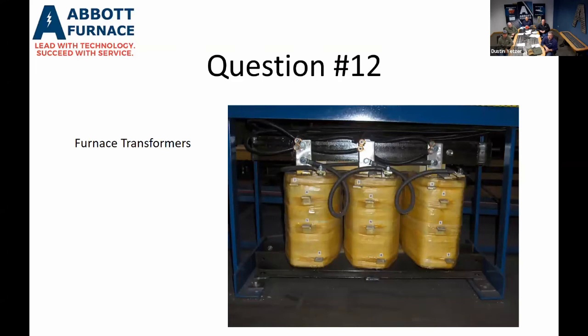You want to look at that zone when it's calling for 100% output and record what the voltage is and the current coming out of the SCR going out to the transformer. You have to determine what size transformer you have in that zone to look at what your max amperage allowed is. Then, as the glow bars wear, the resistance goes up. So if that resistance has increased enough that you're not pulling enough power to heat that zone up, then you're going to have to move up a tap, which is a voltage tap.